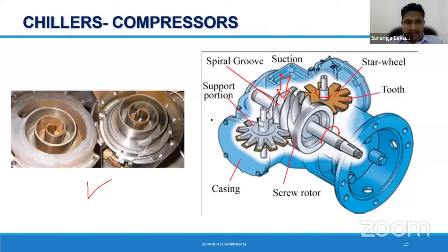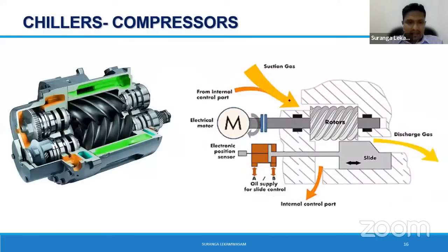But if you want a chiller in the range of 100 to 500 ton, you can find chillers with screw compressors, screw chillers. If you see our local installations, we don't have many bigger buildings. All our chiller capacities are in the range of 100 to 500. So I would say 80% of our installed chillers are screw chillers. You can find single screw chillers, or some manufacturers make twin screw chillers. Whatever it is, the concept is the same, right?